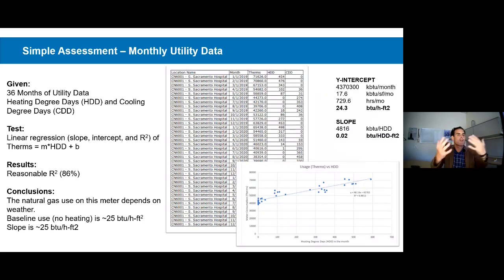So let's start to chunk through some of these. The first data set we always have is the monthly utility bill. There are 2 things that we can do with monthly utility bills. First, we can check for a relationship. When we download utility data, we also get cooling degree days and heating degree days for the months. Now, it is very common to find no relationships. In other words, the stated conclusion would be something like the monthly electrical use has no relationship to the monthly cooling degree days, or the monthly natural gas use has no relationship to the monthly heating degree days.